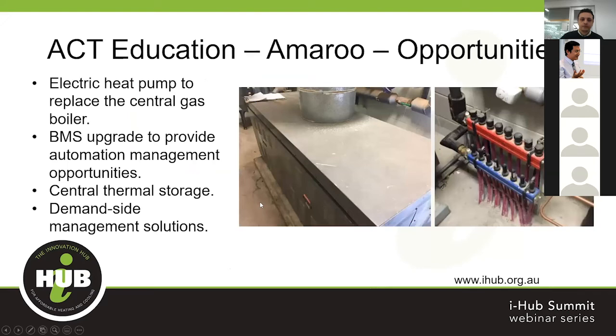Some of the opportunities here—we're very much open to industry coming to us with any suggestions they have for technology and services that would suit these facilities. Is it possible to replace this gas boiler with a heat pump? That may be able to deliver both heating and cooling needs using the already water-cooled slab. There's also a BMS upgrade, so how do we better use some of these existing systems, maybe with model predictive control or something, plus central thermal storage and demand side management solutions.